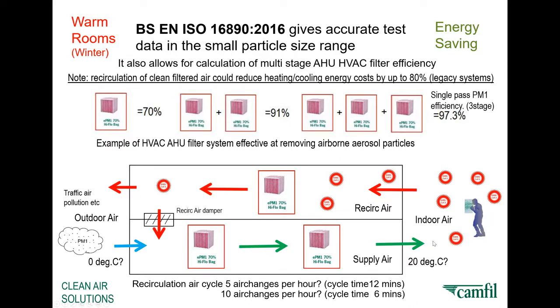Very high efficiencies. So if you take into account also the air change rate, 5 air changes, that means every 12 minutes you're changing that air in the indoor space. And if you boost it to 10 air changes per hour, that would be every 6 minutes. So if you introduce a proportion of that air back into here, it used to be 80% recirculation, 20% outdoor air to keep the oxygenated levels and remove and dilute carbon dioxide.